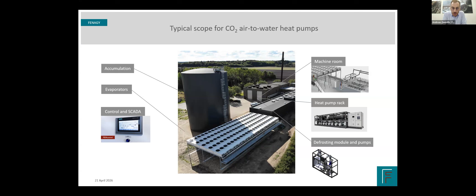A typical CO2 air-to-water heat pump is our bread and butter when it comes to projects and systems. A system that has it all would include a hot water storage. You would see those white panels with black dots, which are the evaporators or fans absorbing heat from the ambient air. All of that is controlled by SCADA and a control system, which is FENAGY IP or knowledge. All the equipment is inside a machine room where the heat pump units are located, along with smaller units we call defrosting modules, which remove ice from the evaporators and keep them operating even in very cold conditions.